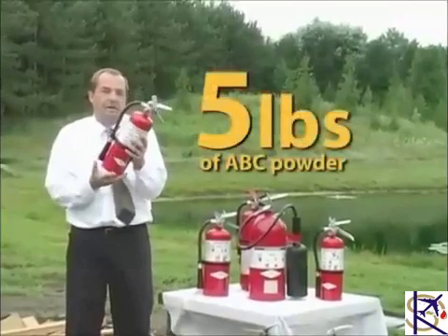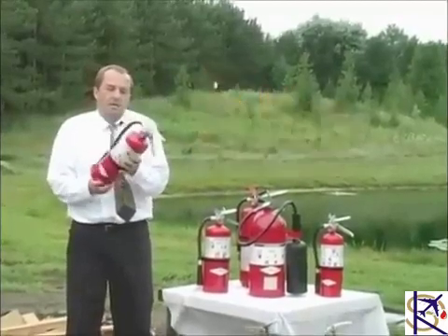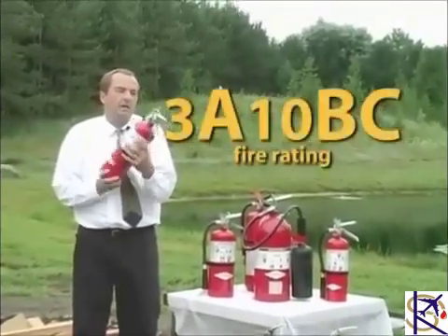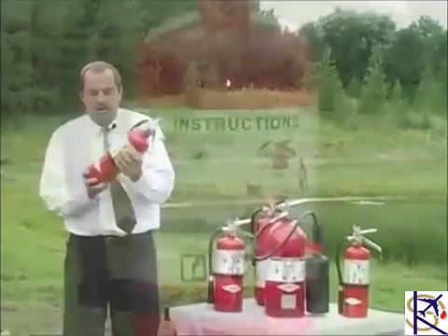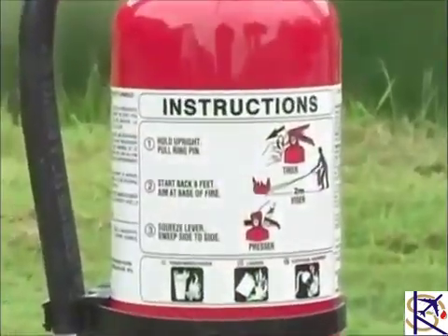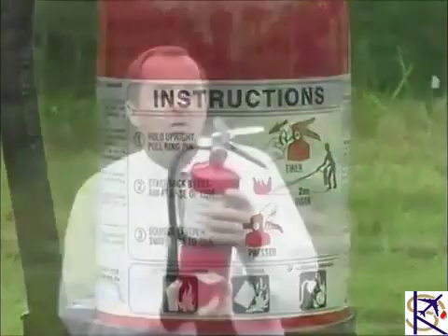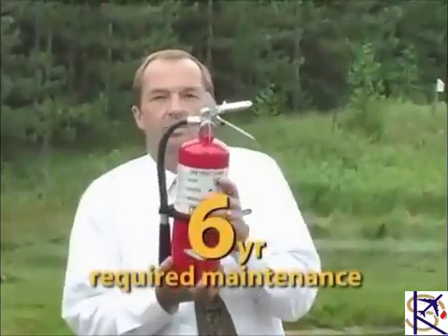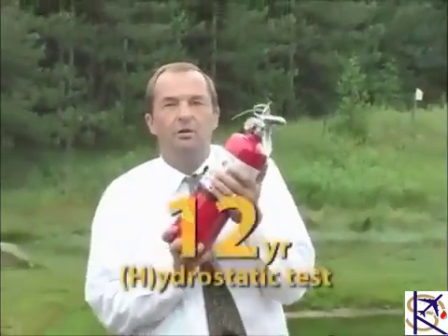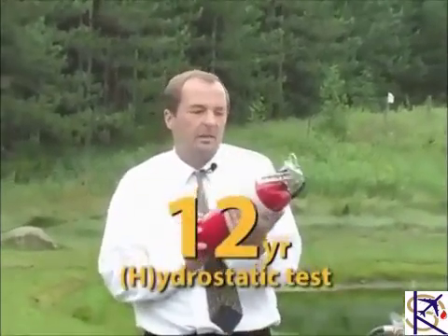5 pounds of ABC powder, 3A 10 BC rating. Very good quality extinguisher, very easy to use. This extinguisher requires maintenance 6 years from when it was made and a 12-year hydrostatic test.